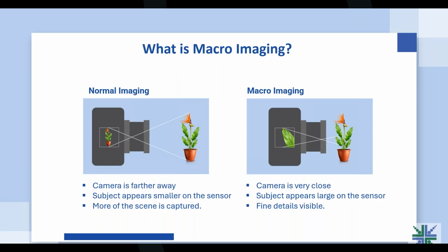This approach is well suited for imaging larger anatomical areas, general inspections, or situational awareness where depth variation is relatively small compared to the working distance. But in contrast, macro imaging fundamentally changes the optical setup. The camera is brought much closer to the subject, and the system is optimized so that the region of interest fills most of the sensor. This maximizes spatial resolution on small features. Higher magnification brings more detail but less focus. That limitation is depth of field.